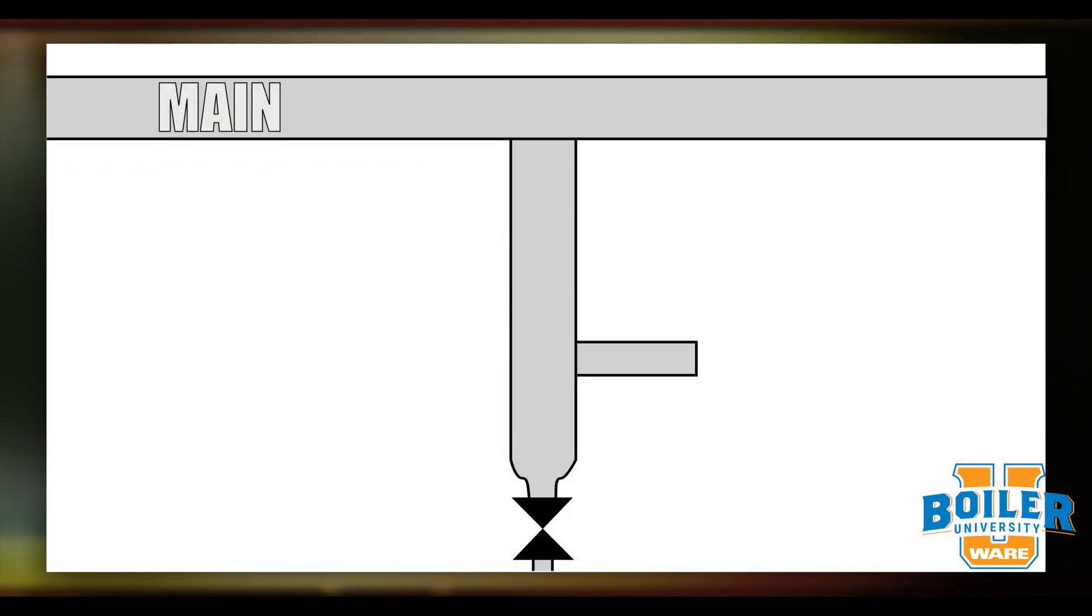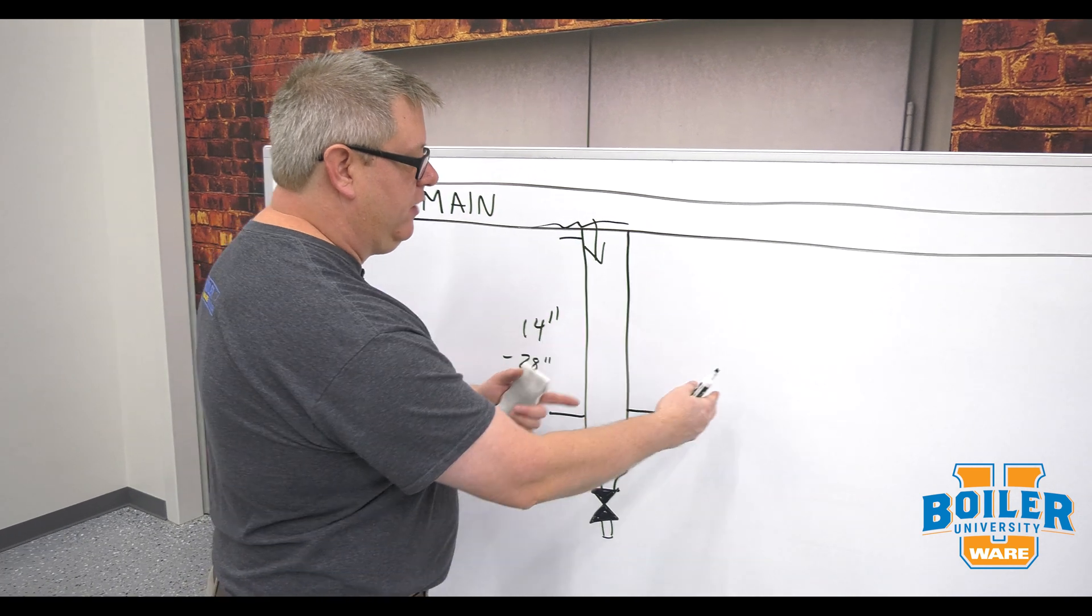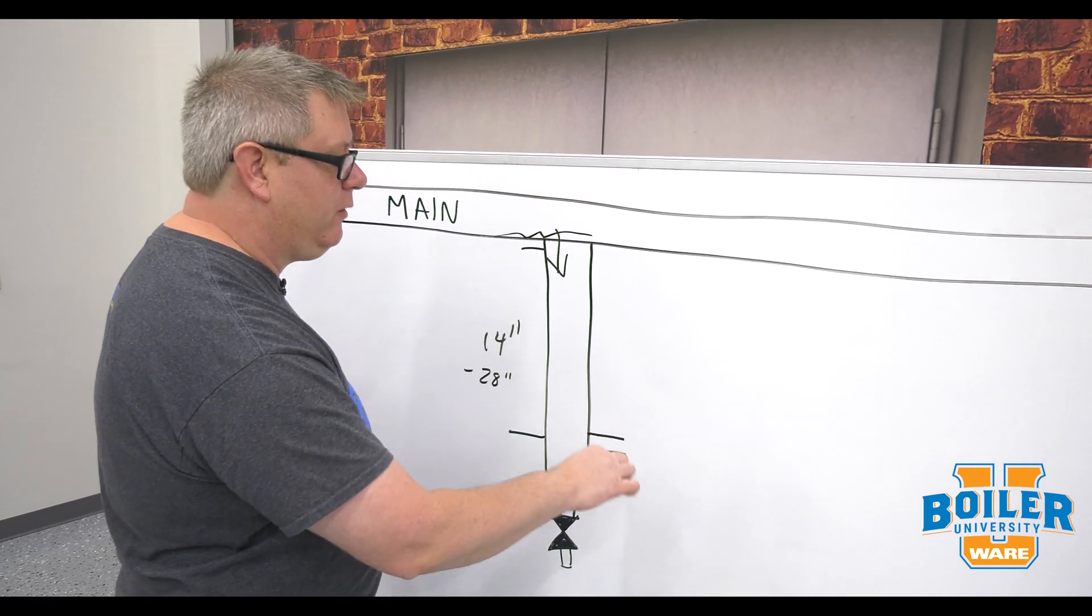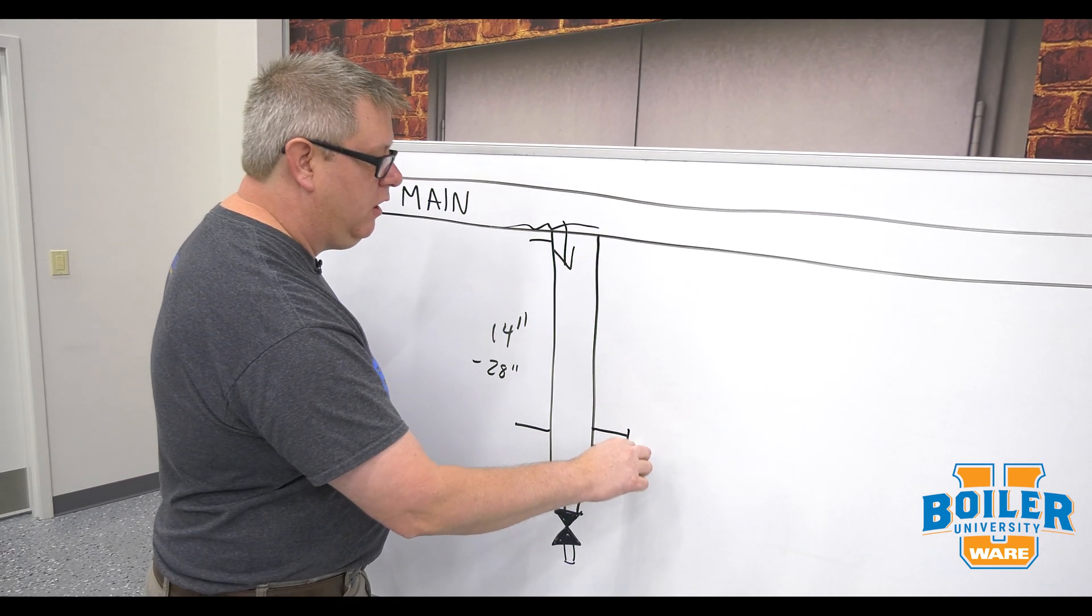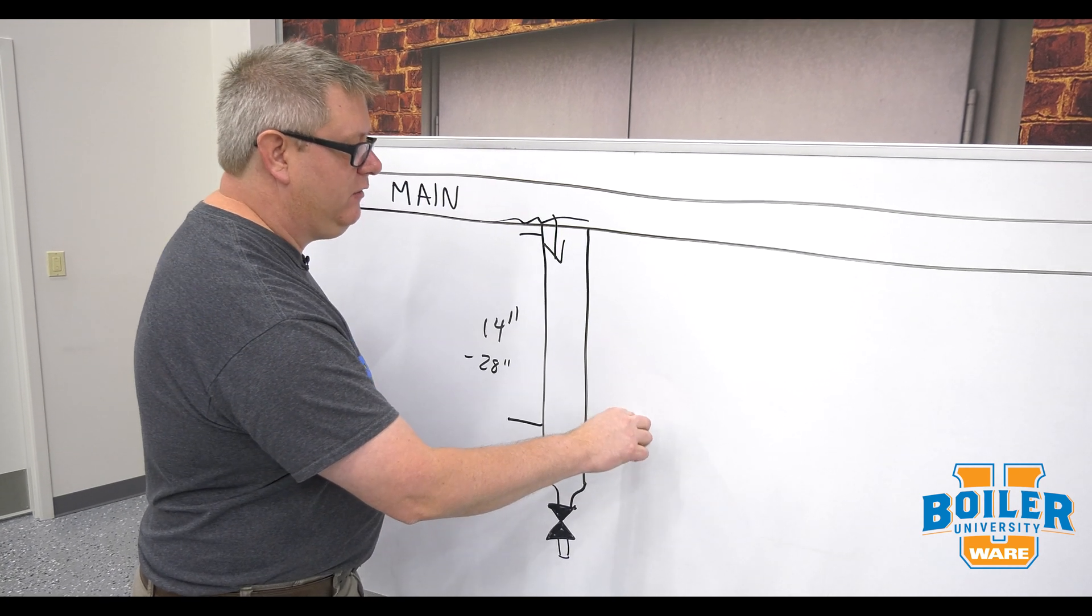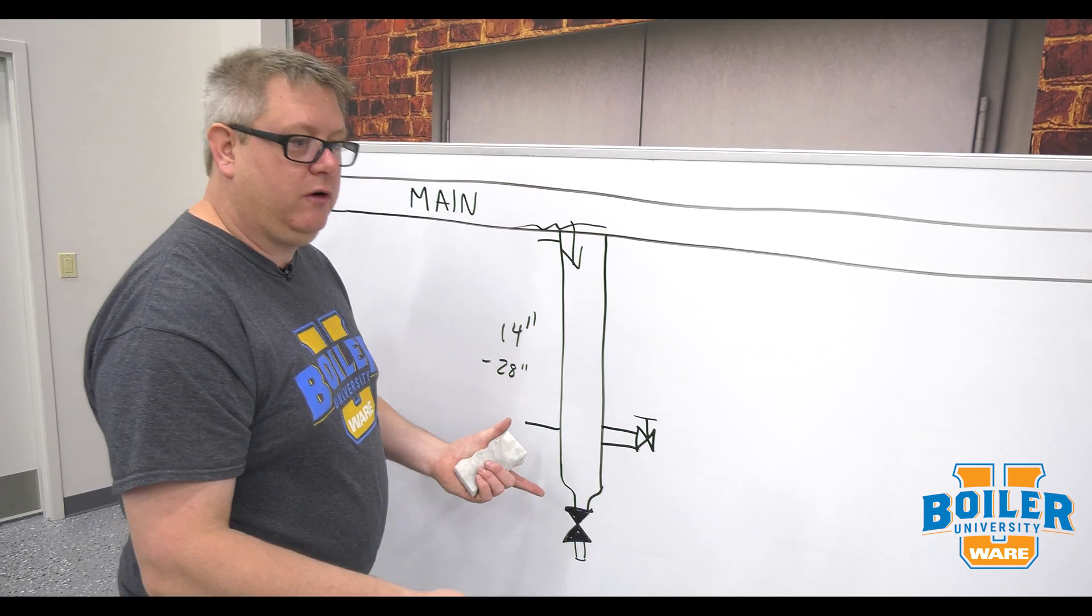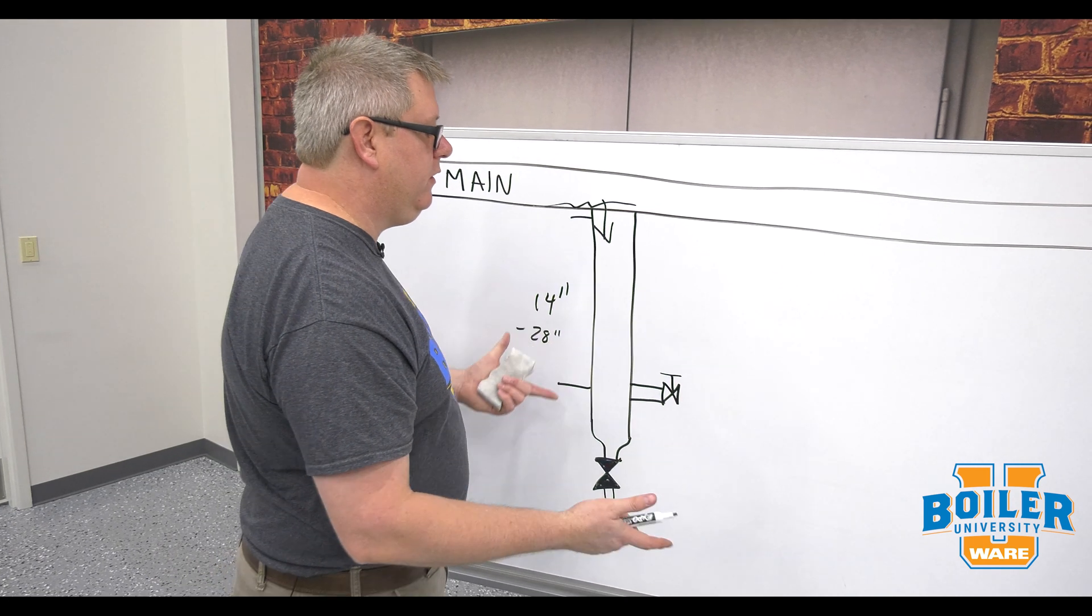So when we come off the side of the drip leg for our trap we want to be off the bottom so we've got a pocket there for dirt so it doesn't go directly into our trap. The first thing we're going to have on that takeoff for our trap is a manual isolation valve and that's so we can service do what we need to with this system.